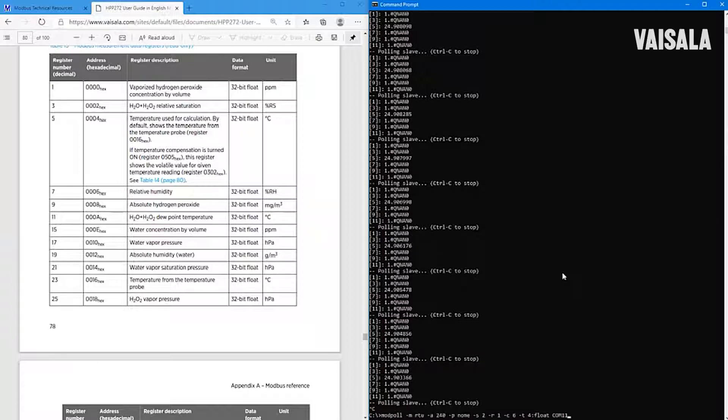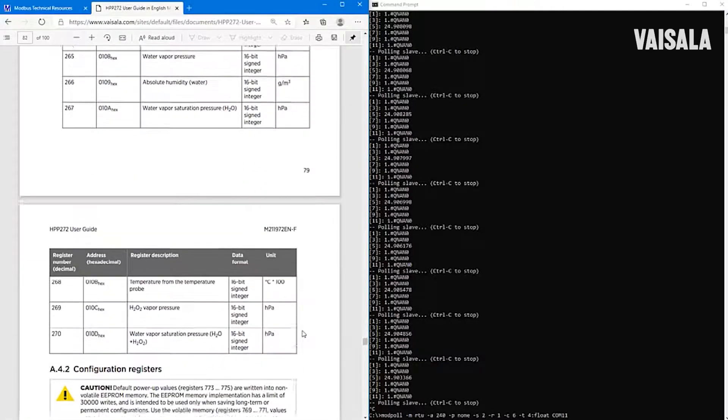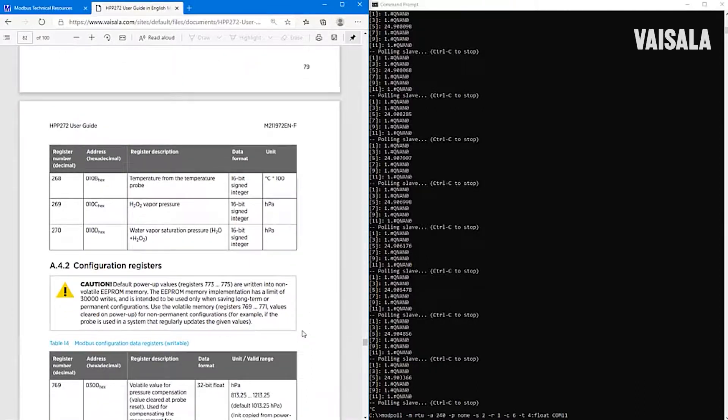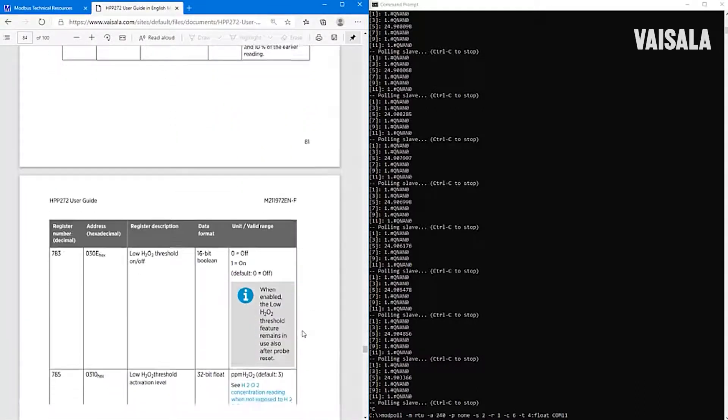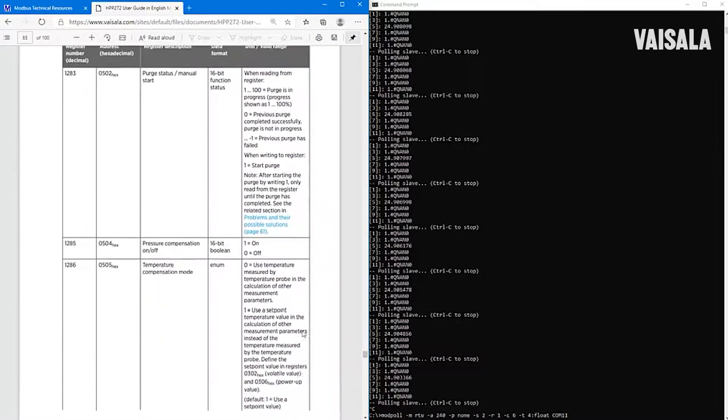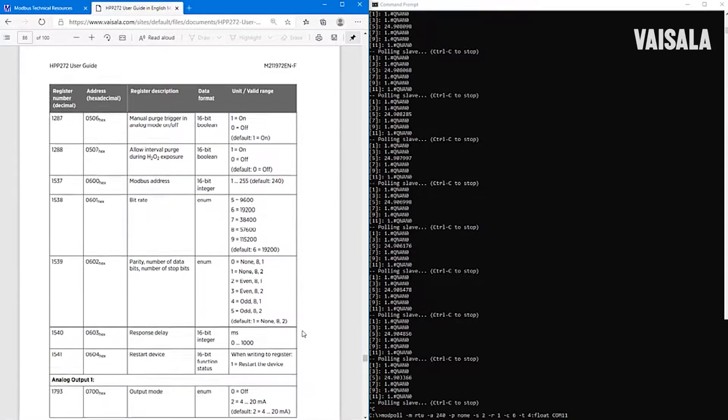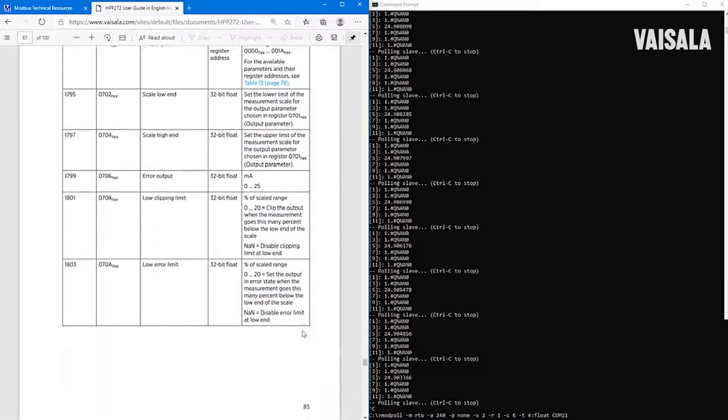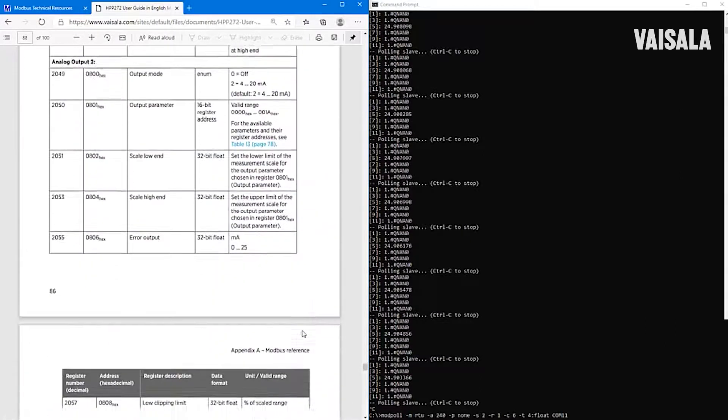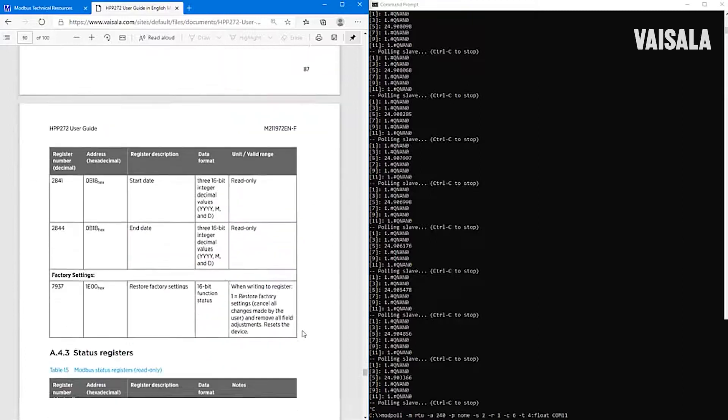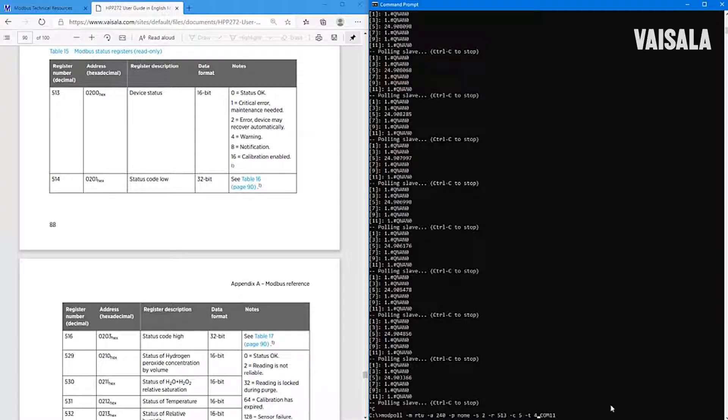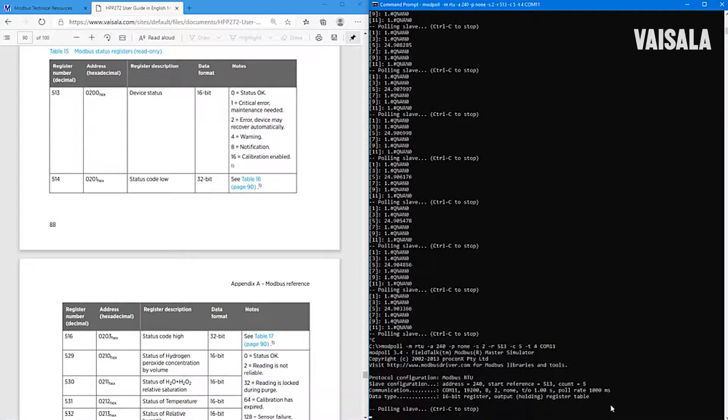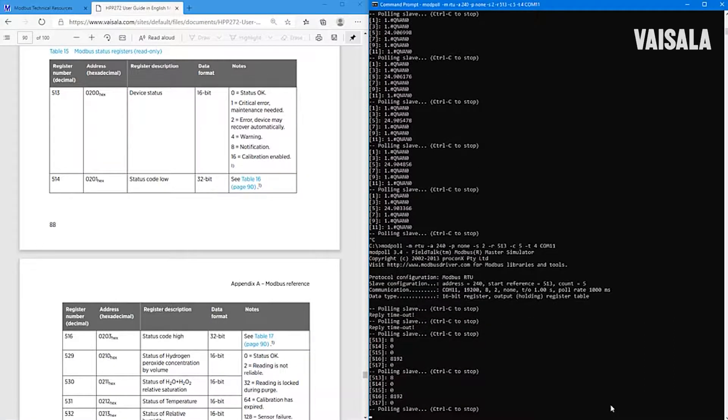Of course, we can ask it from the probe by using Modbus protocol, starting from register number 513. And we are going to read one, two, three, four, five values. Why five? Because we want to read integral values here. And the first register is 16 bits, but the second is 32 bits, and also the third. So with this command, we are able to read these three registers.